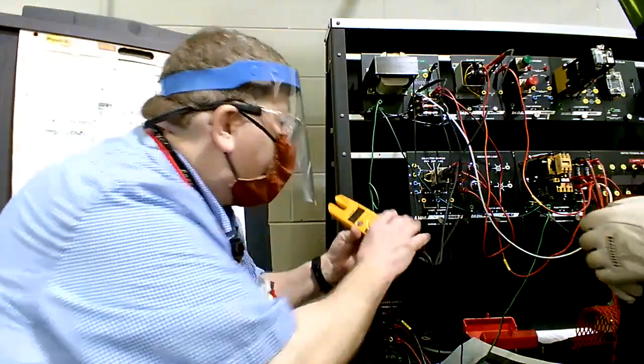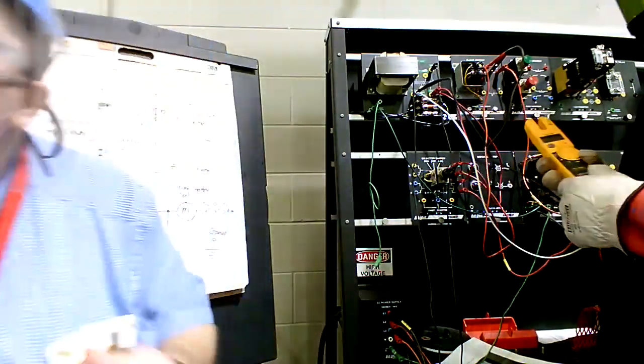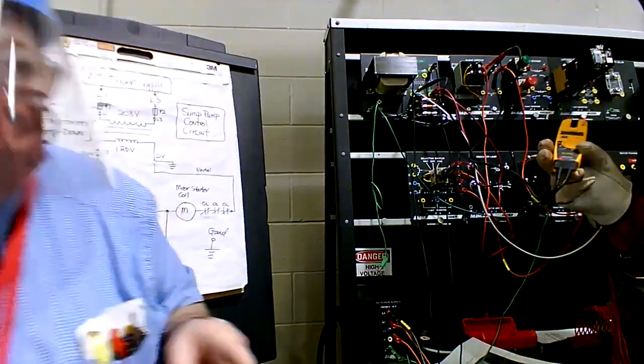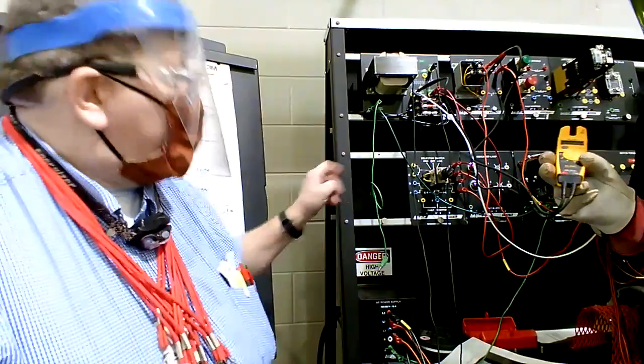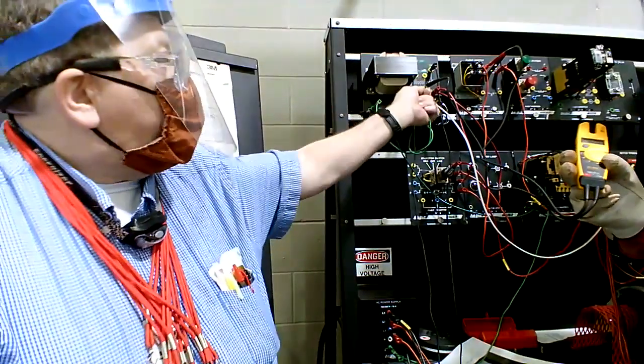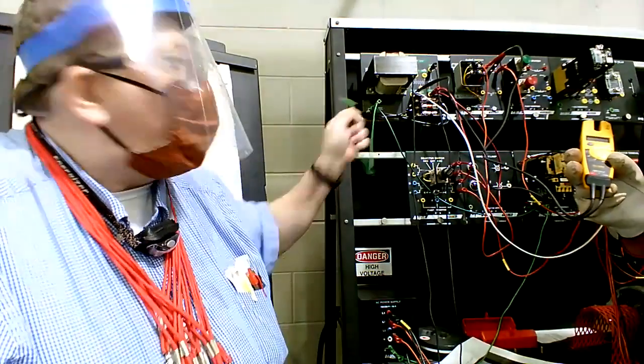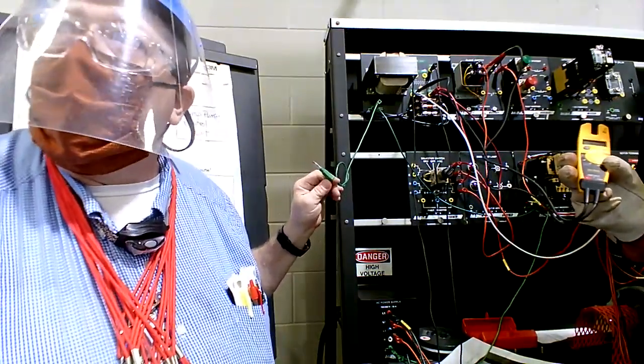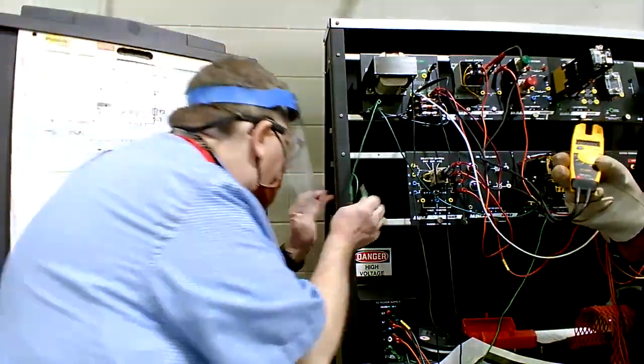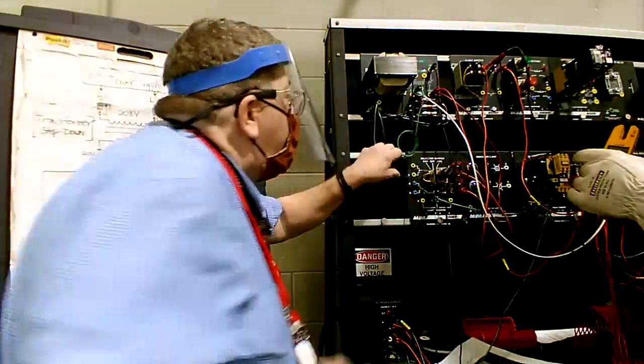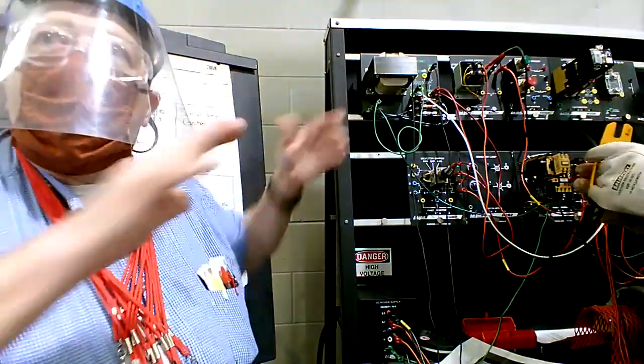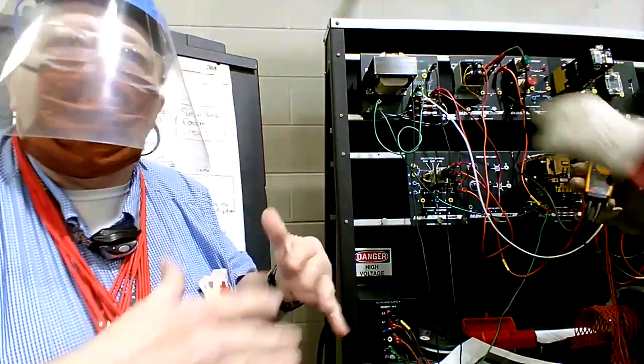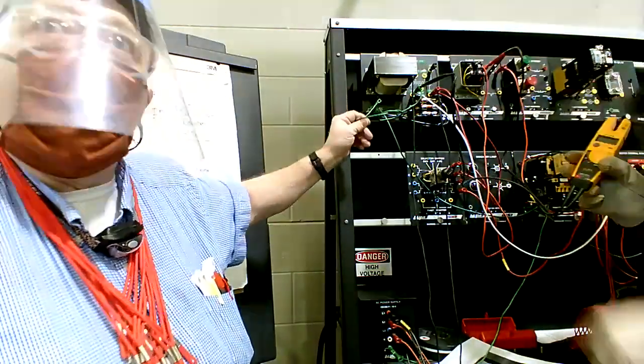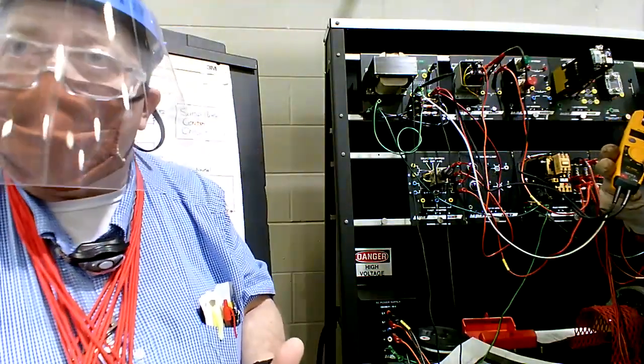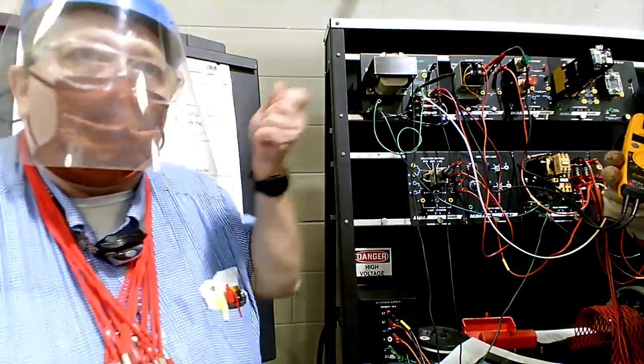So here's what can actually happen in reality. Hold your meter. Sometimes, look, everybody watch. Everybody watching? Sometimes the connection between the transformer neutral and ground can be rusty. It can get loose. If you get a bad connection between the neutral and the ground, like a rusty situation from moisture that gets in there, and you get some resistance in there, then it's produced a problem for you: you cannot use ground as a reference point anymore.